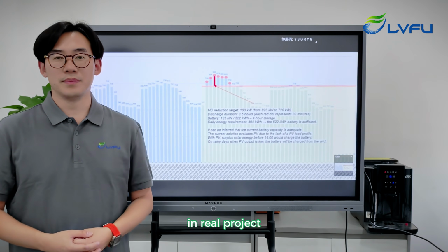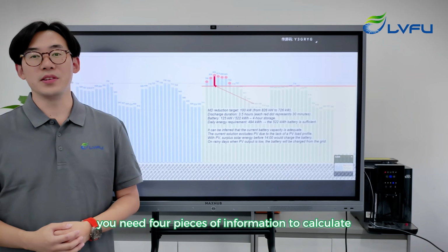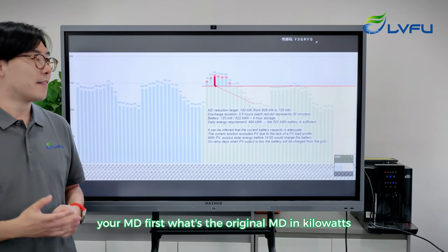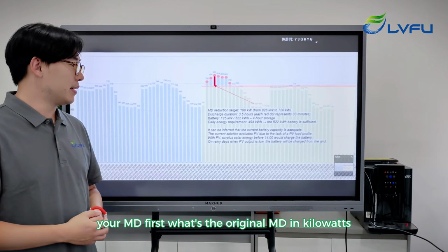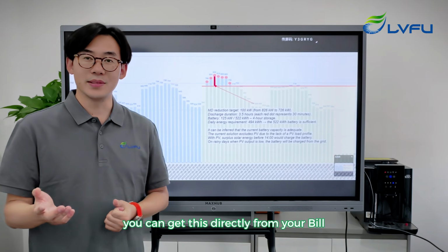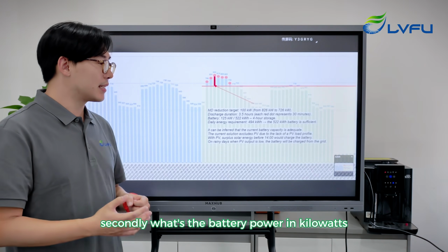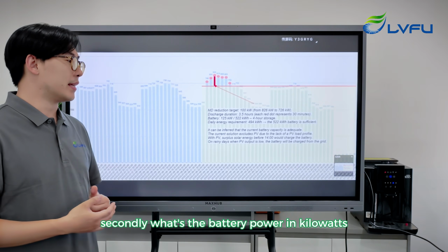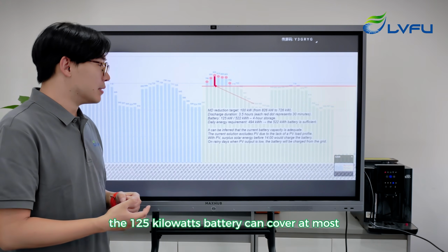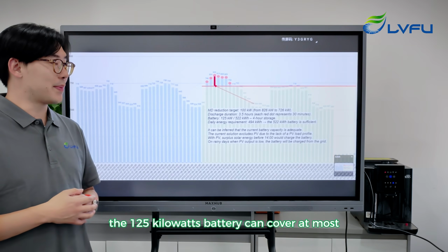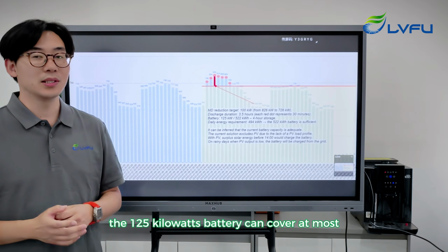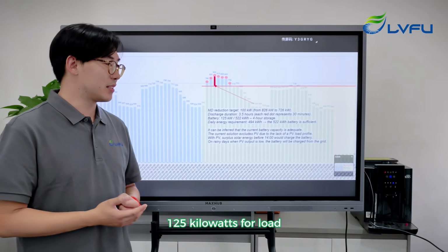In a real project, you need four pieces of information to calculate your MD. First, what is the original MD in kilowatts? You can get this directly from your bill. Secondly, what is the battery power in kilowatts? For example, a 125 kilowatt battery can cover at most 125 kilowatts of load.